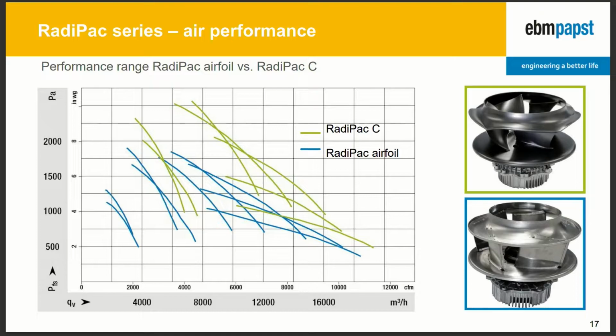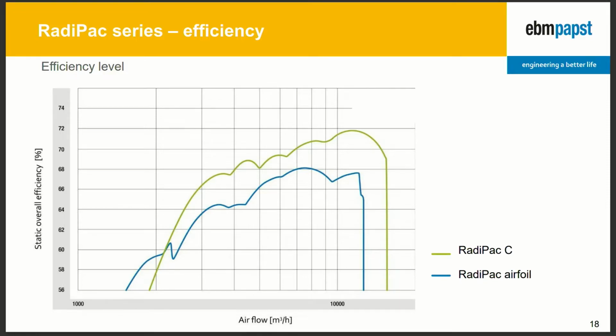So the blue lines indicate the old fan family. It's a pressure development over the air volume. And the green curve, this is the new RadiPac C. We call it RadiPac C because of the composite impeller material. So you see that we increased the air performance in respect to flow and also mainly on pressure. So we can operate them at quite a high RPM level. Efficiency level, this is the envelope of the static overall efficiency, wire-to-air efficiency, over the fan airflow. And you see that the envelope shows over the whole range an increase in efficiency by 3 to 5%. 3 to 5% points means at the end an energy saving of 7-8% compared to the old one.